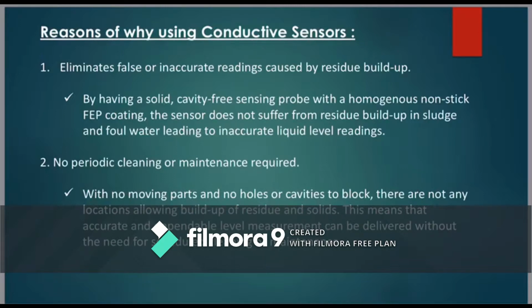Second, no periodic cleaning or maintenance required. With no moving parts and no holes or cavities to block, there are not any locations allowing build-up of residue and solid. This means that accurate and dependable level measurement can be delivered without the need for scheduled cleaning or maintenance. This means that this conductive sensor has low maintenance.